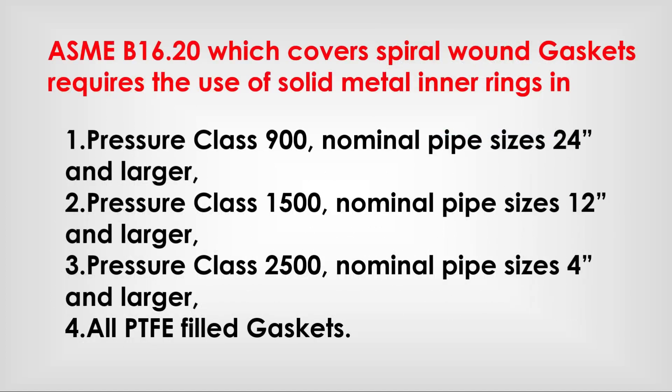ASME B16.20 covers spiral wound gaskets and requires the use of a solid metal inner ring for: pressure class 900, nominal pipe sizes 24 inch and larger; pressure class 1500, nominal pipe size 12 inch and larger; pressure class 2500, nominal pipe size 4 inch and larger; and all PTFE-filled gaskets.